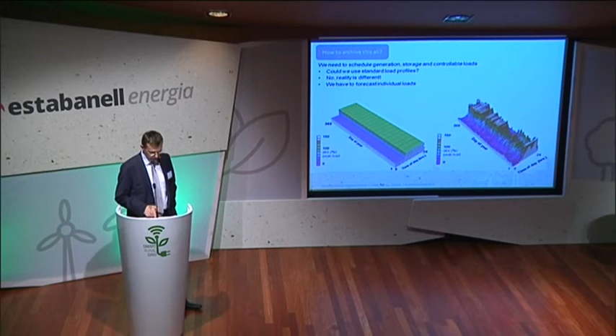One example, this is from Rosenheim, 3 years ago in 2014, so it's quite a long time, but it's real data. What you can see is the blue one is the active power, and it's negative from the perspective of a transformer. That means it's feeding back into the grid. Over a really sunny day, there's so much photovoltaic installed here that it will feed back. In the night, the red one is directly behind the blue, so blue is not zero - there is a little consumption, but overall we have a problem here that it is feeding back.